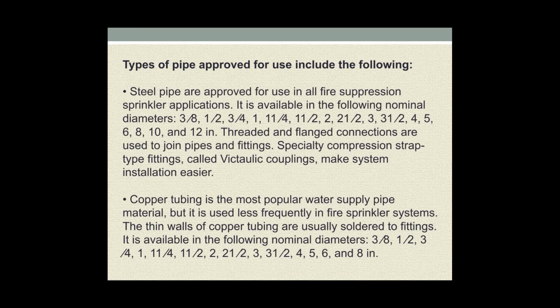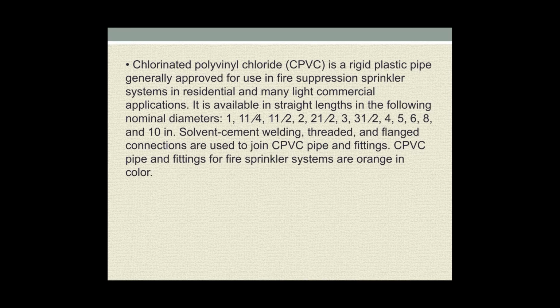Copper tubing is the most popular water supply pipe material but is used less frequently in sprinkler systems. The thin walls of copper tubing are usually soldered to the fitting, and it is available in the following nominal diameters. Chlorinated polyvinyl chloride, or CPVC, is a rigid plastic pipe generally approved for use in fire suppression sprinkler systems in residential and many light commercial applications. It is available in straight lengths in the following nominal diameters. Solvent cement welding, threaded, and flanged connections are used to join CPVC pipe and fittings. CPVC pipe and fittings for fire sprinkler systems are normally orange in color.